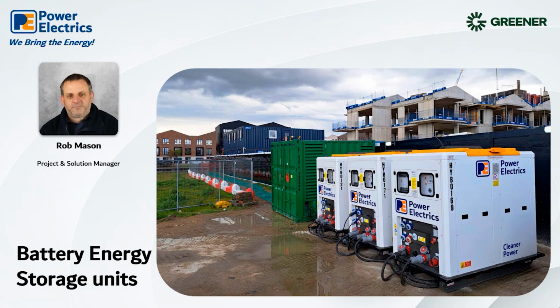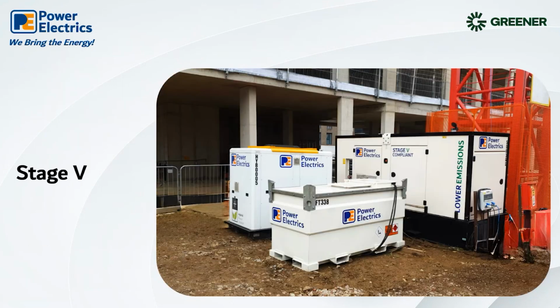One of the major benefits of running controlled loads is the sustainable efficiencies that can be gained. The generators and most energy sources have a particular level that would make them efficient. Take the Stage 5 conundrum. Efficient running is taken to be around 70-75%. Unfortunately, a site load, or any electrical load, is never that standard. Using battery systems enables us, through storage, to do peak shaving and basically enable generators and power systems to be run at an efficient load.